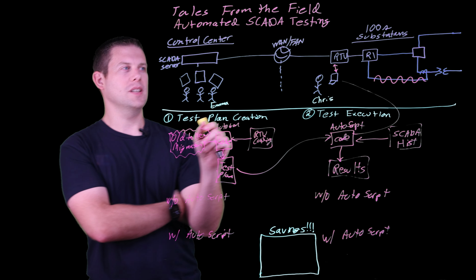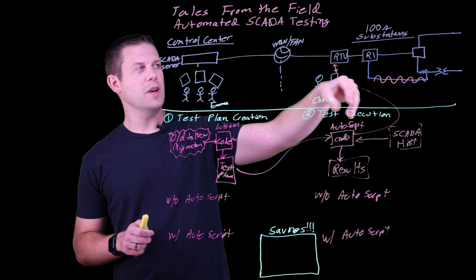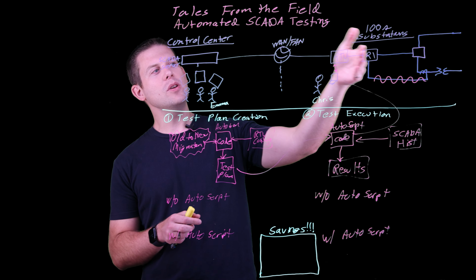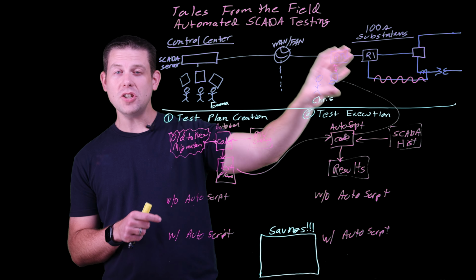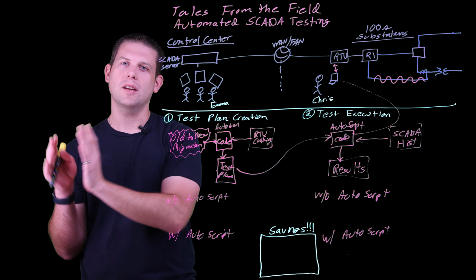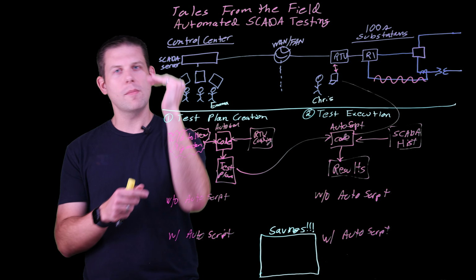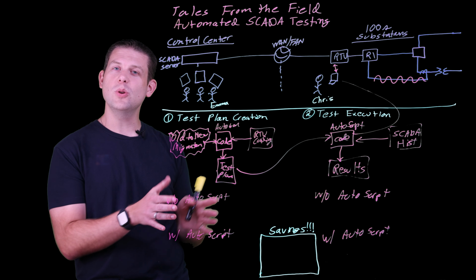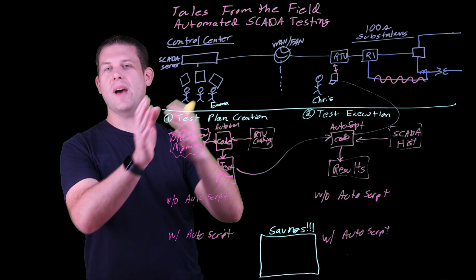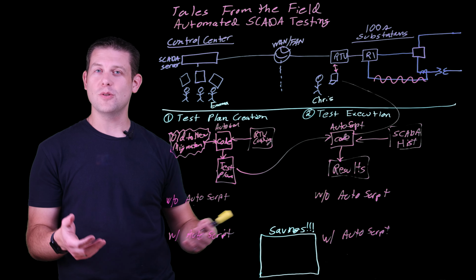If you had to test a substation end to end, you're checking out the relays, making sure they're performing their protection logic accordingly. Then when you look at the integration from the station to some head-end control center, you have to go point by point and make sure all those values and controls are going back and forth properly, that the values are matching.